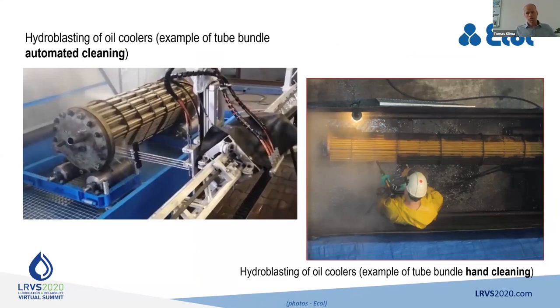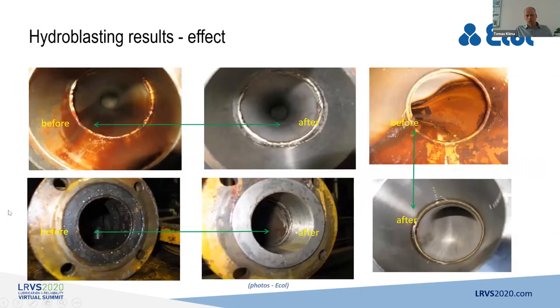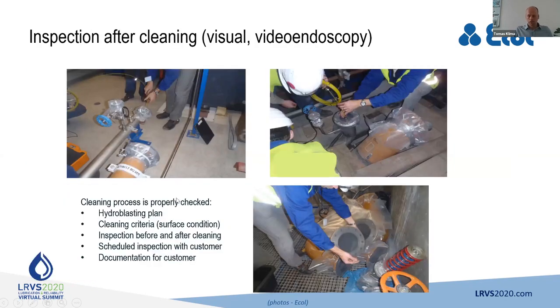The components are cleaned manually in specific open tanks. Of course, the coolers, cooler bundles in that way, or we have developed an automatic cleaning method, which we do in our workshop. And what about the result? You see that after the cleaning, where the high pressure water penetrates all the deposits, the surfaces are totally clean. They are without varnish, without corrosion, without any welding residues or left machining particles, pure clean, and also very well possible to inspect with video endoscopy or just by yourself making the inspections.